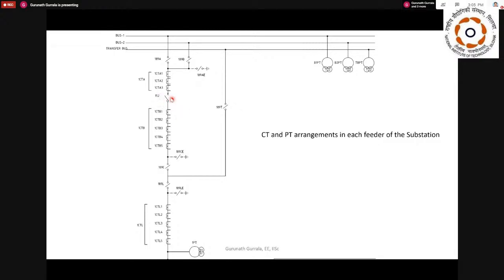In the middle, the number 52 indicates the circuit breaker, and 89 indicates the isolators, with CTs also numbered here. The letter A at the end with E means earth switch. Although we haven't physically implemented earth switches, we've created electronic switches with interlocks made available so you can create the earth switch emulation in this setup.